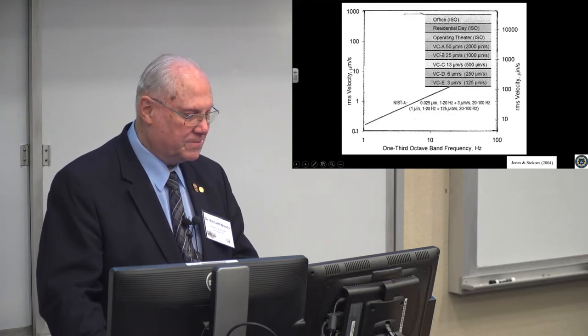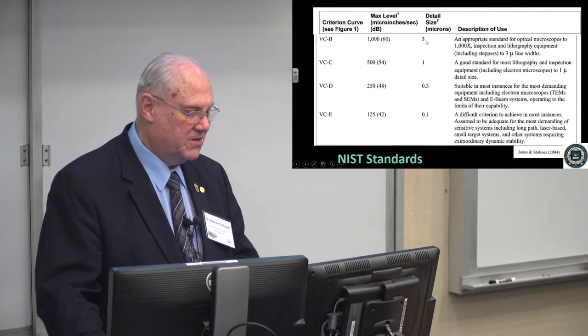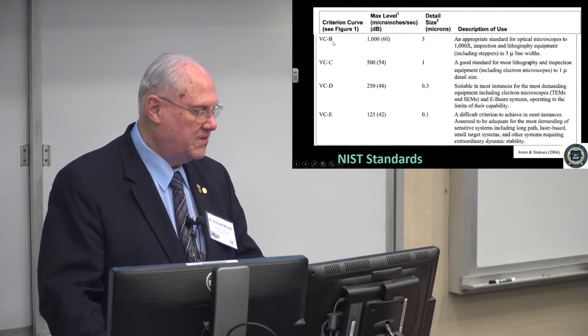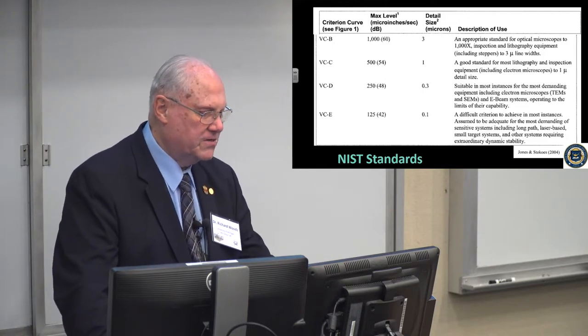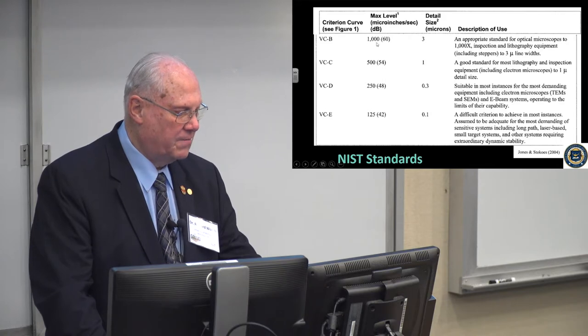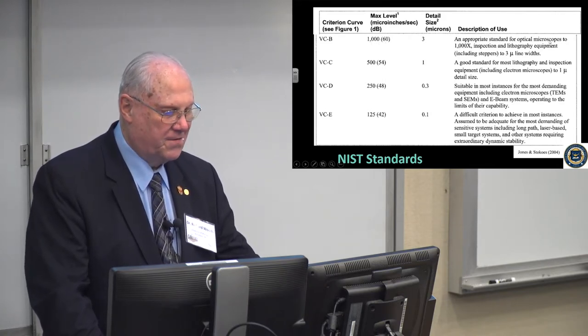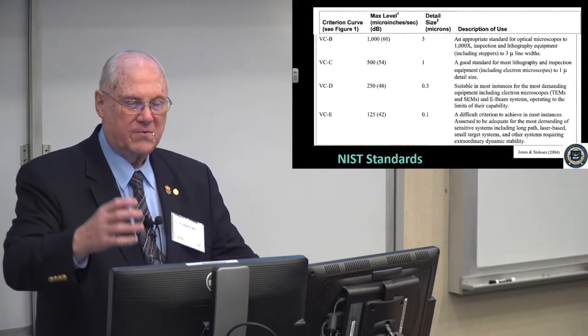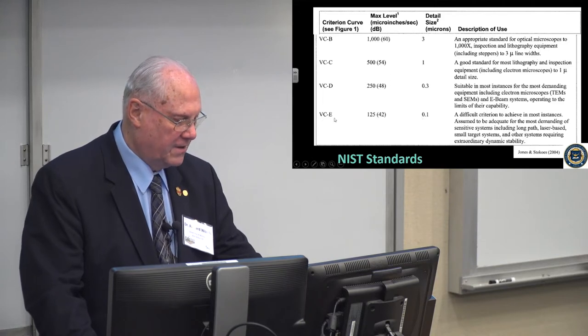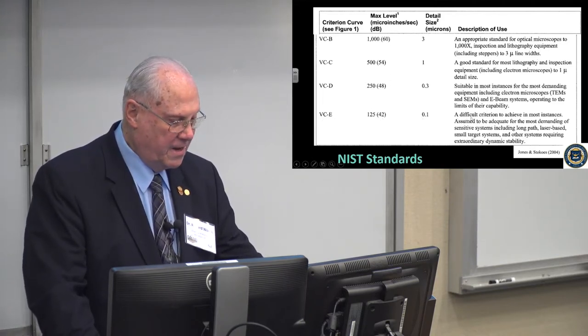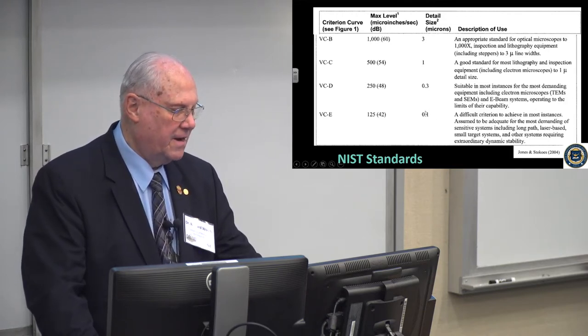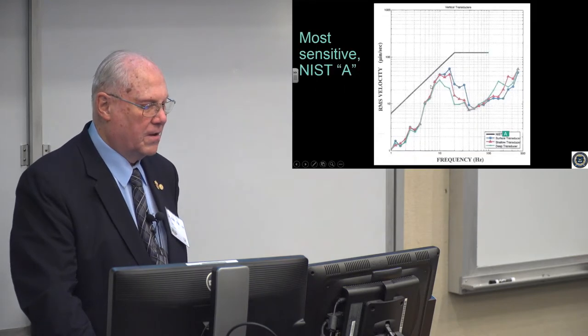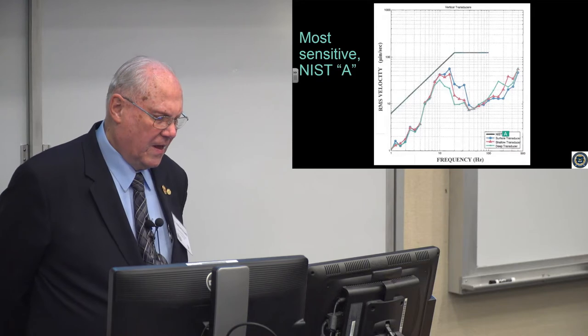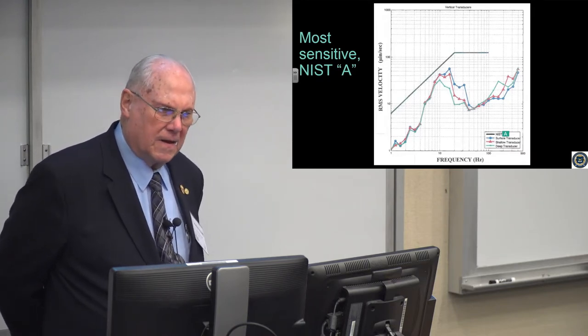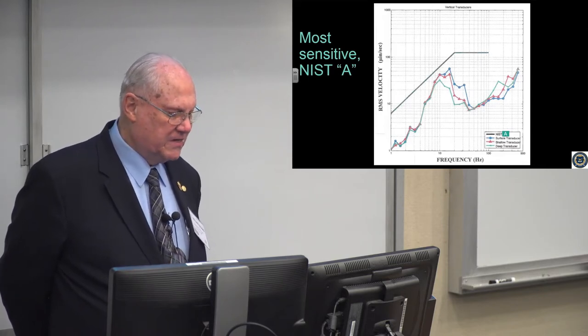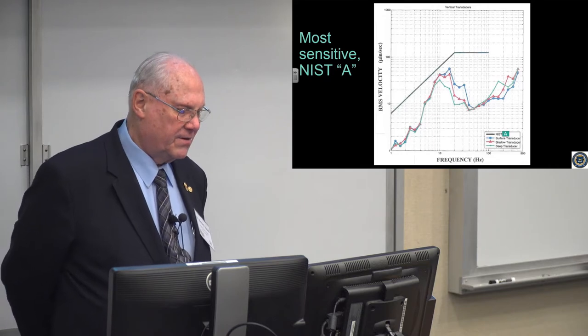There are various levels of limits. For instance, this VCB from NIST, the National Institute of Standards and Technology, with the maximum level indicated here, an appropriate standard for optical microscopes. In laboratories, you need that sensitivity. For extremely difficult sites, VCE is a difficult criterion to achieve in most instances, and NIST has proposed the most sensitive limits for siting instruments and research facilities on the ground.